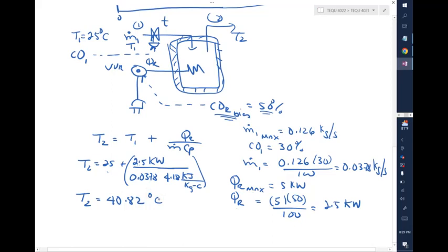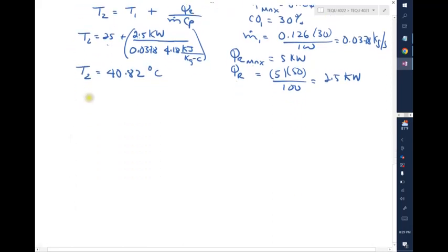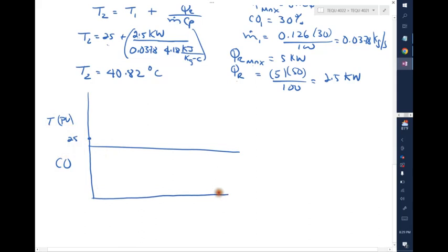So the story is this. That's the first dynamic that we run on this. So it will look like this. Let's say that the initial value is 25 degrees. So we are starting the temperature on the system, which we call PV, and the CO was at 0. It was off. That's why the initial temperature is 25. As soon as we start this, we put this at 50%. This is time, and the temperature will gradually start to increase to finally arrive at a new steady state.